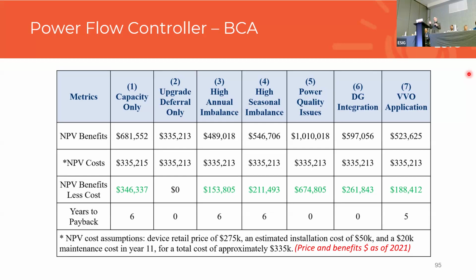Similarly, if we look down at the NPV cost assumptions, this is in 2021 dollars, but the retail cost of the device was $275K. There was an estimated $50K installation for the pad, getting everything out on site, and then a $20K maintenance around year 11. I believe this is the device that has a 20-year lifespan.